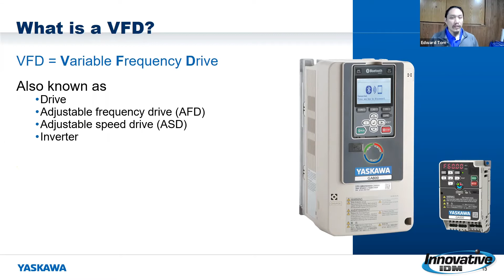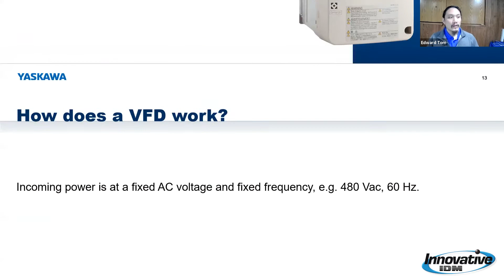Now, I will take a step back here real quick. I threw out VFD. I think I threw out drive out there. What exactly is a VFD? Well, in this case, a beige box, but black box that's out there that is controlling my speed. And a VFD is ultimately a variable frequency drive. It's been known by other terms, and I've used it interchangeably as a drive or adjustable frequency drive, adjustable speed drive, and the slight misnomer, but it's also been called an inverter. And I'll get into the topology of the VFD and why some people refer to it as that. But those are some of the names that you'll hear for a VFD or a drive.